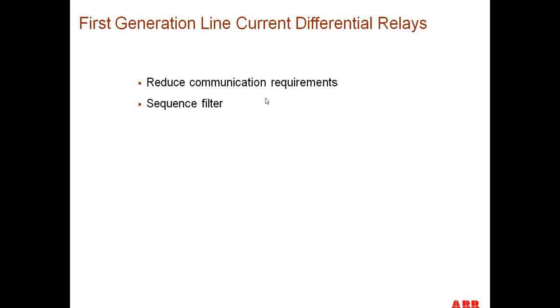So the first generation of current differential relays had very, very reduced communication requirements. As a matter of fact, the communication between the two ends of a line was simply a twisted pair of number 14 or number 16 or number 18 wire between two ends of a line. Thus the length of line that this would protect would be less than 2 miles long for the maximum line length for this first generation of current differential relays.